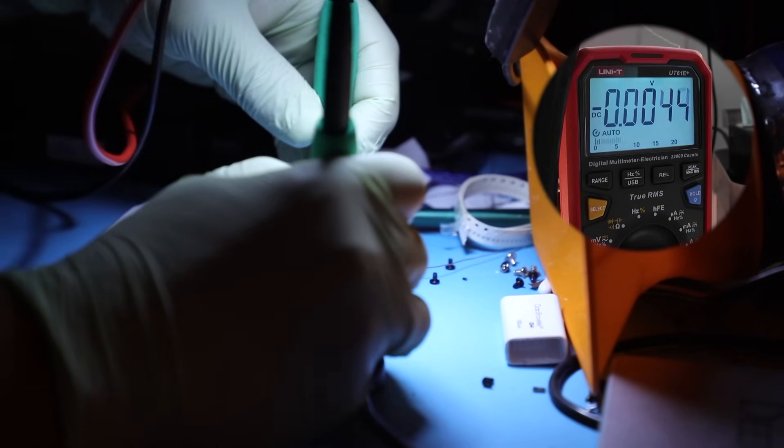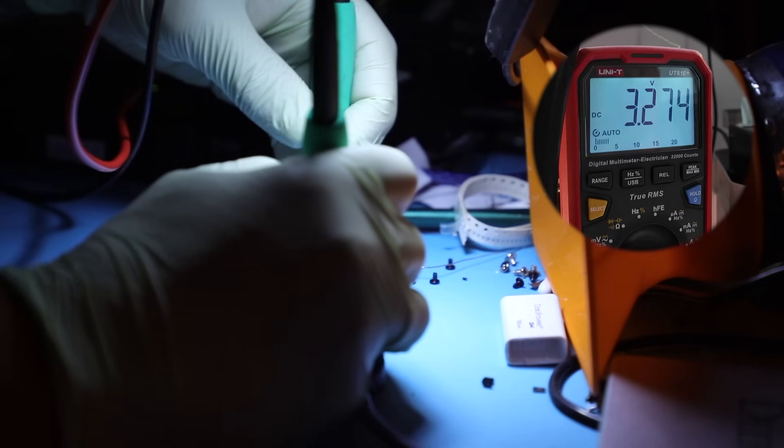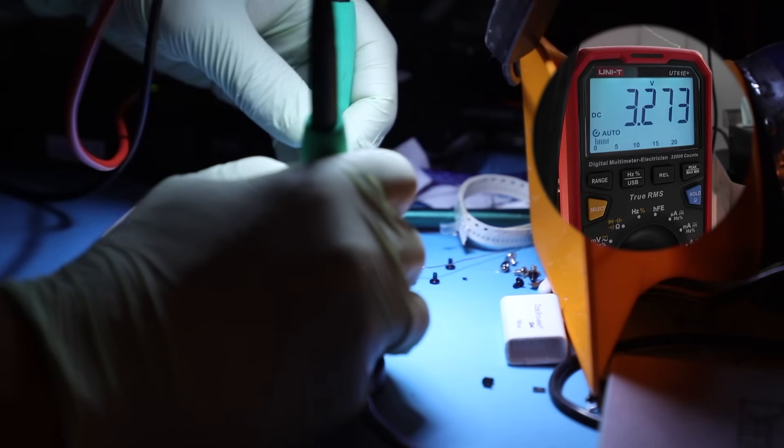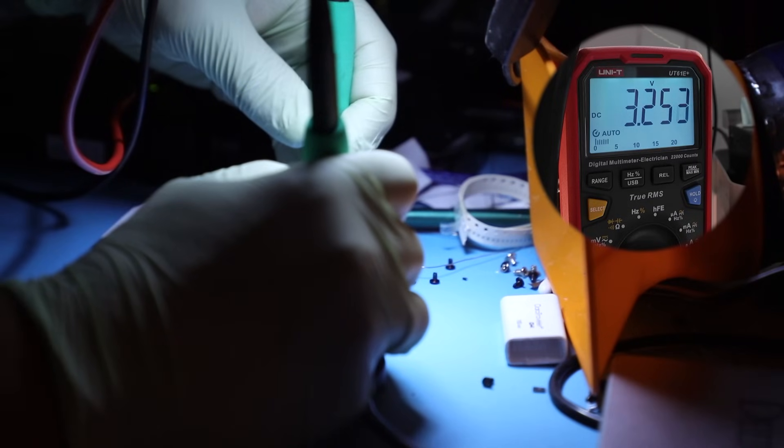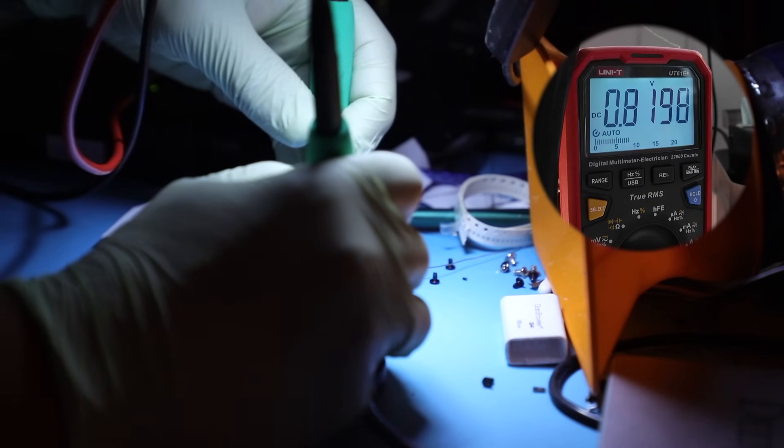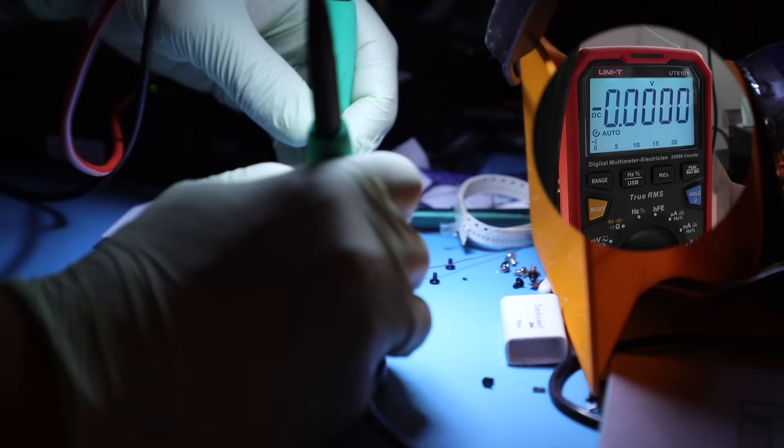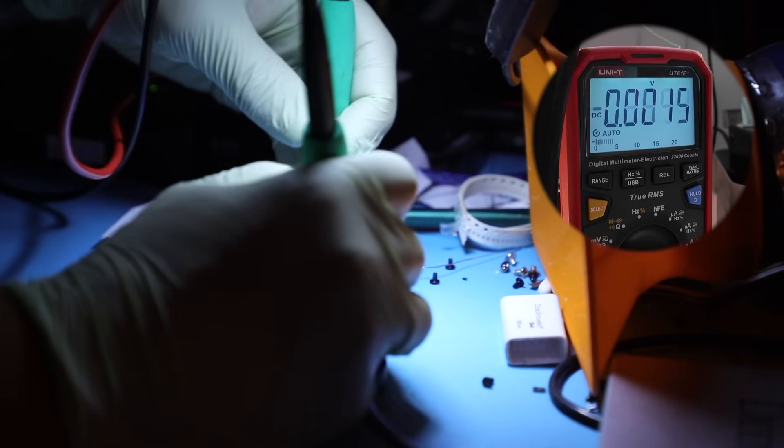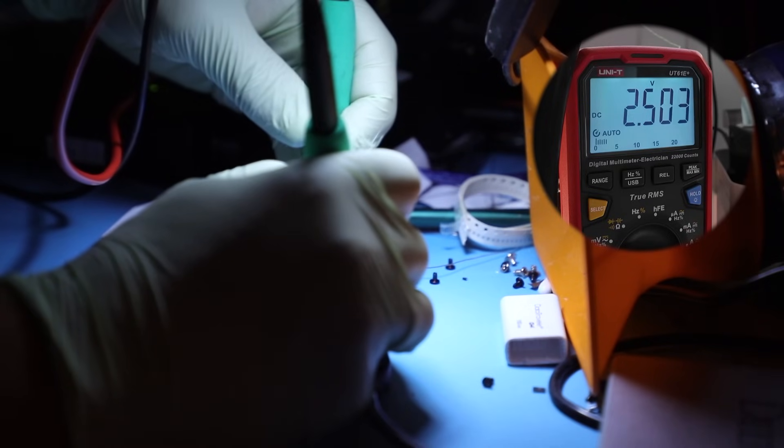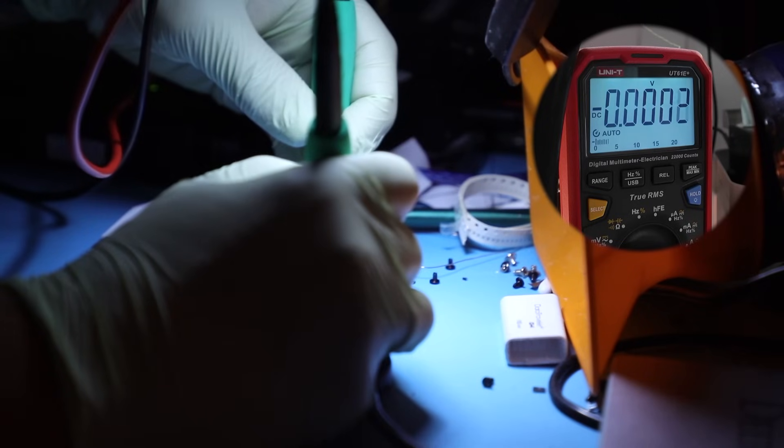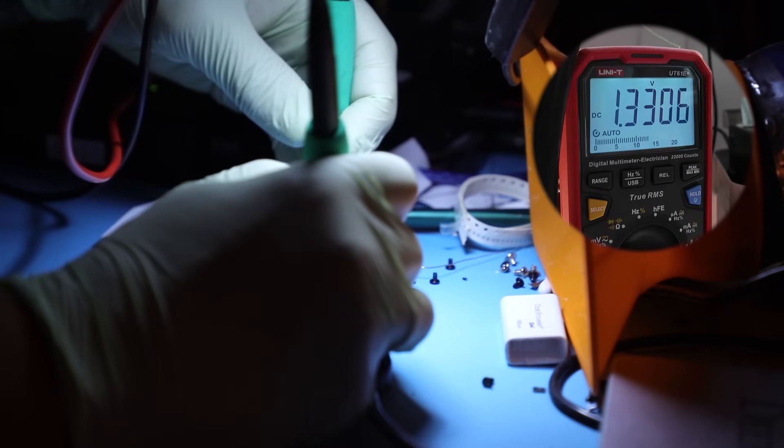So we were getting 3.3 before, that's going in. 3.3, 3.3 is here, 0.8, that's already good. 0.8, 3.2. On our coils we got 0.8, 2.5. There's a capacitor, 2.5. This coil, 1.3. And this coil, 0.8.